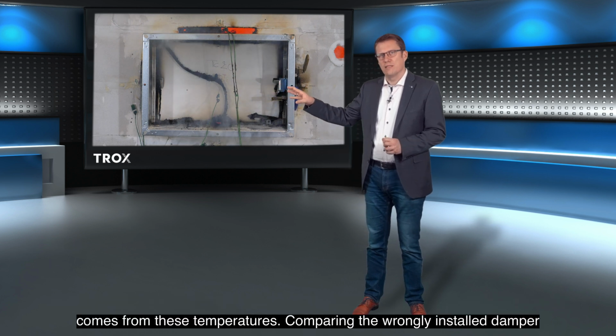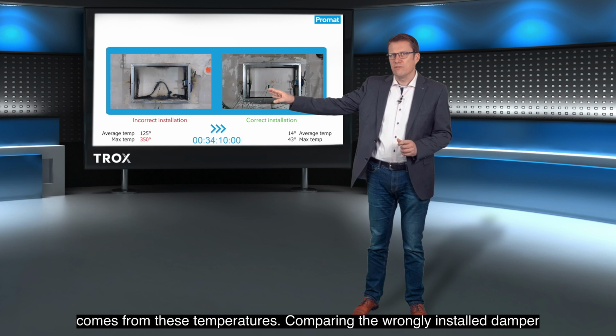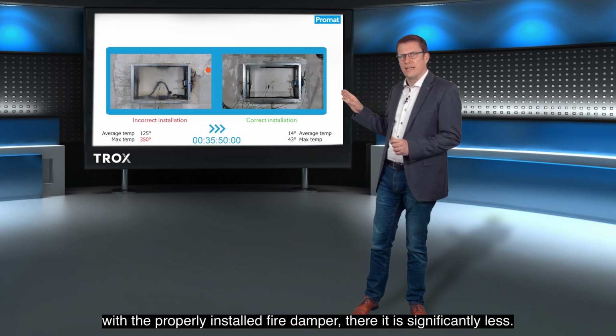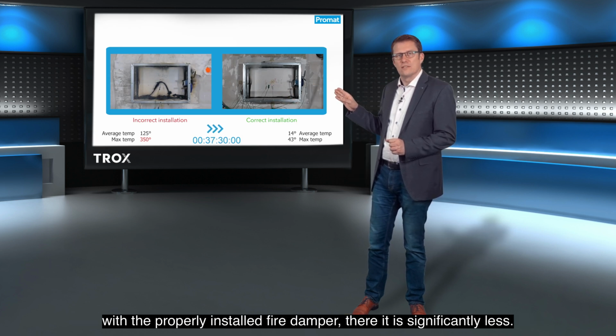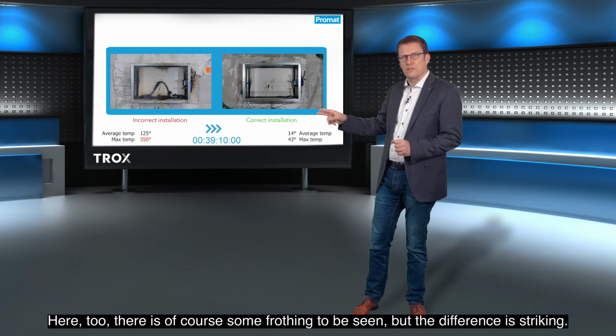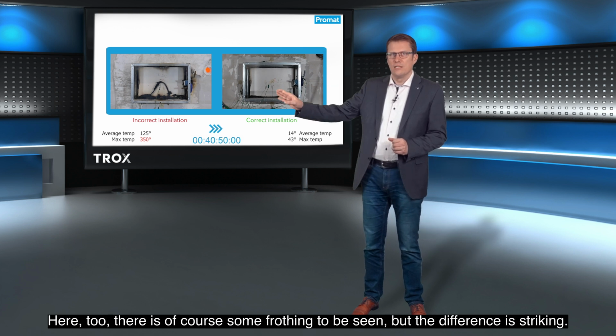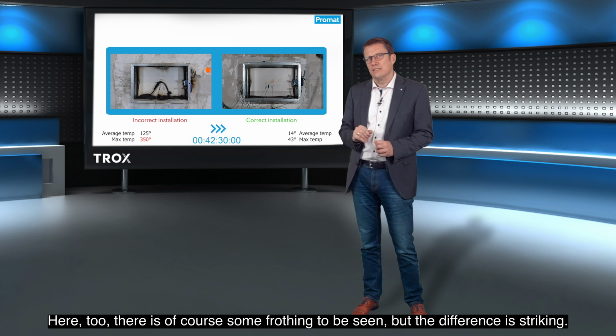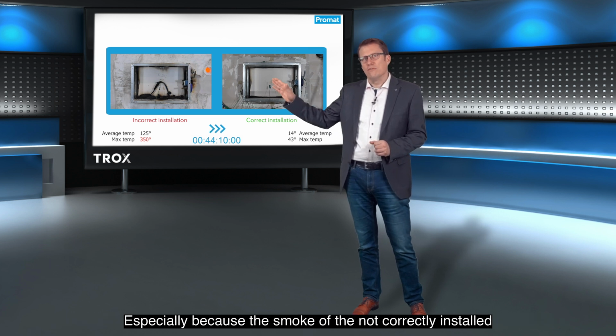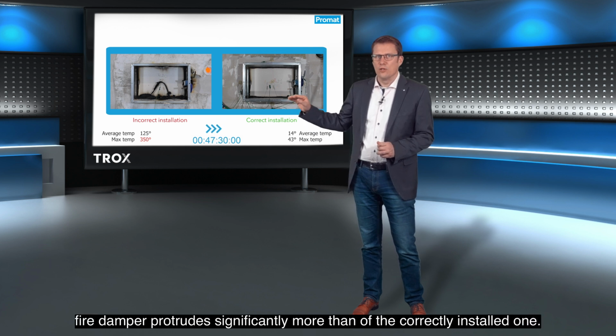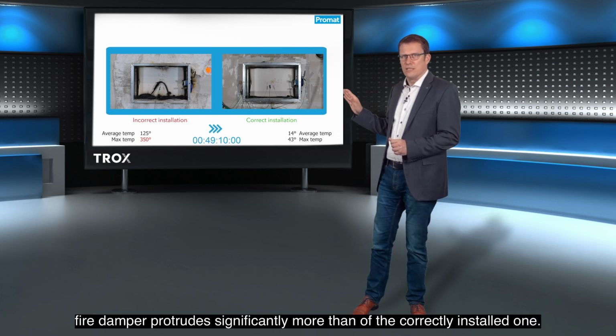Comparing the wrongly installed damper with the properly installed fire damper, there it is significantly less. Here too, there is of course some frothing to be seen, but the difference is striking, especially because the smoke of the not correctly installed fire damper protrudes significantly more than of the correctly installed one.